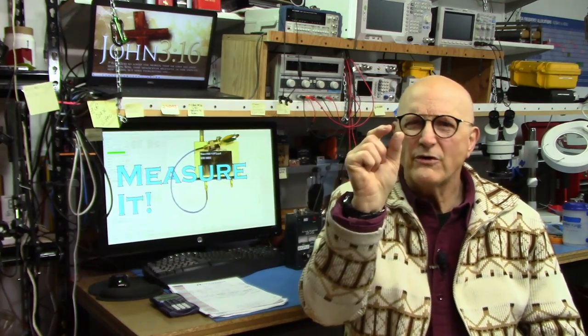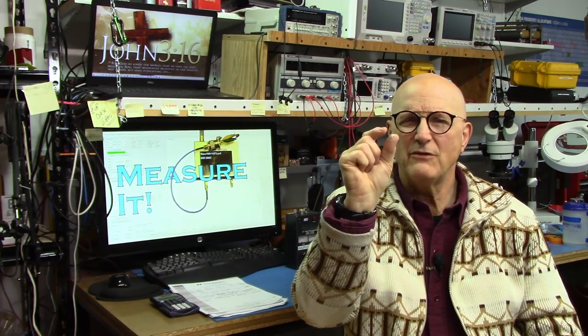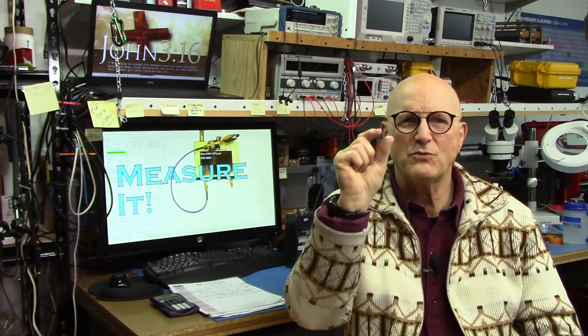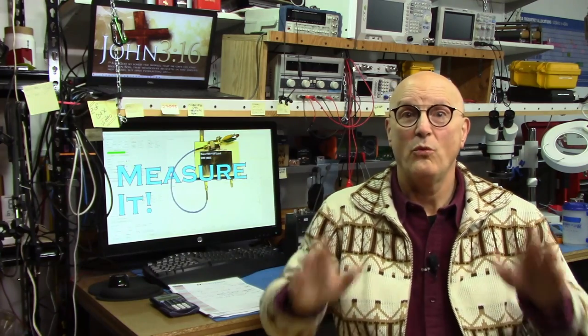And we have to use some sort of means to connect the component to the test instrument. I mean, I had a 1/4 inch or 6.4 millimeter piece of 16 gauge wire soldered across an end connector. A dead short, right? Not actually. It was a 9 nanohenry inductor. We have stray inductance. So how significant are these strays to our measurements?